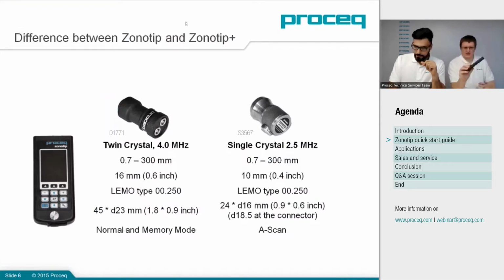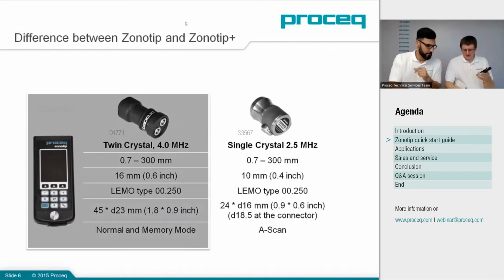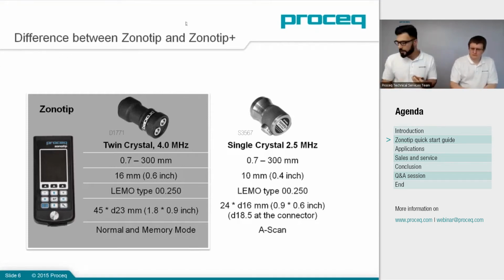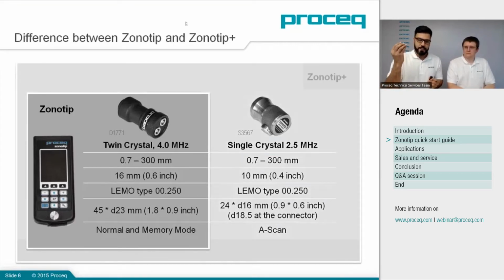We've got the Zonotip here. Here's the device, and Ali will tell you what the difference between Zonotip and Zonotip Plus is. Sure. We've got both of the devices set up here. The main difference is that with Zonotip you have the standard twin element transducer at 4 MHz, and with the Zonotip Plus you have, in addition, the single crystal 2.5 MHz transducer and the A-scan functionality. We will cover during the applications both standard mode for thickness measurement, memory mode, and of course the A-scan.